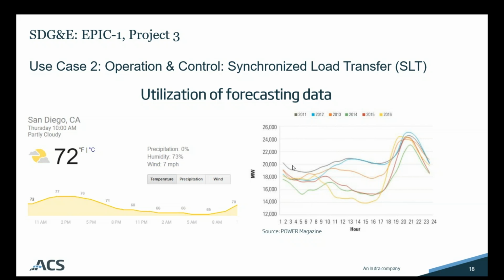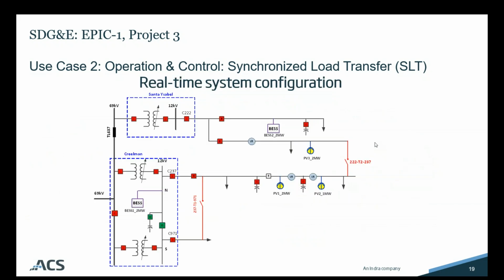So, however, there are times that system violation issues may not be able to be mitigated from either using automatic resource control or from forecasting analysis. As we all know, events can happen on the distribution system that will cause us to think in a more real-time fashion. So that leads us to real-time system reconfiguration.